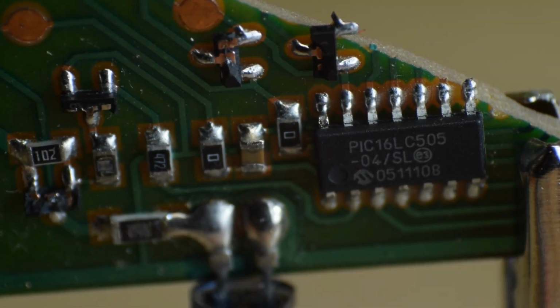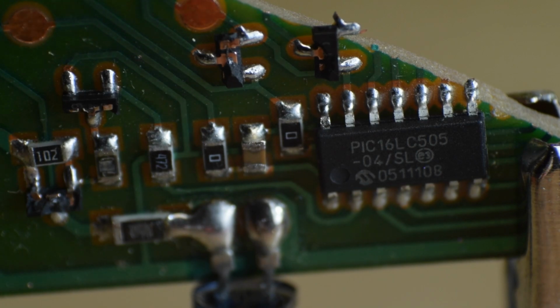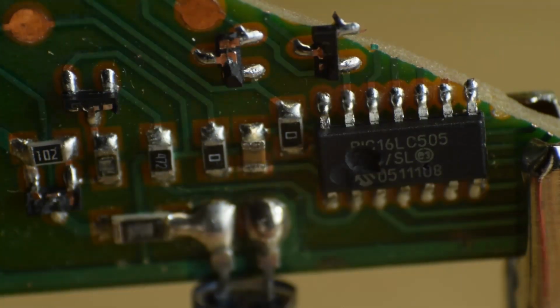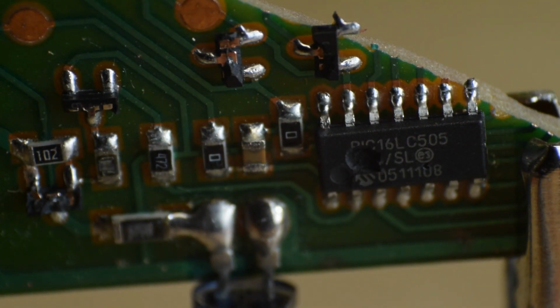To exceed the pain threshold of 1 milliamp at 5000 volts, we would need a resistance below 5 megaohms. No cable got anywhere close to that in any test, which to be honest was quite a disappointment. This still does not mean that all those cables are safe for measuring high voltages. Please do not risk your life to save a few dollars and just get something actually certified for the voltages you intend to use it with. Furthermore, wear, damage and external conditions could make the conductivity higher.